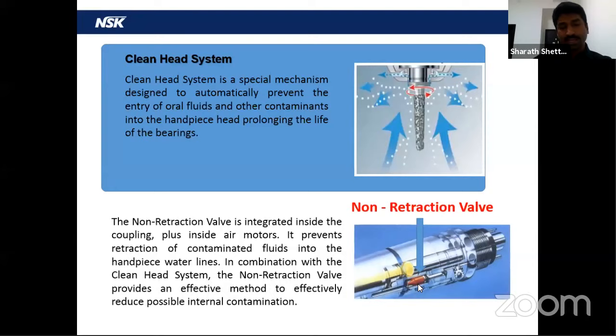How does this happen? Again, as you release the foot control during an operation, this valve closes, and it makes sure that the reverse flow of fluids from the patient's mouth does not enter the handpiece. Water flows from the tubing through the handpiece to the patient's mouth. As soon as you release the foot control, this valve closes and the water inside the handpiece remains stagnant. It prevents the reverse flow of these fluids into the handpiece. So this is a very, very important protection which has to be in each and every dental handpiece.